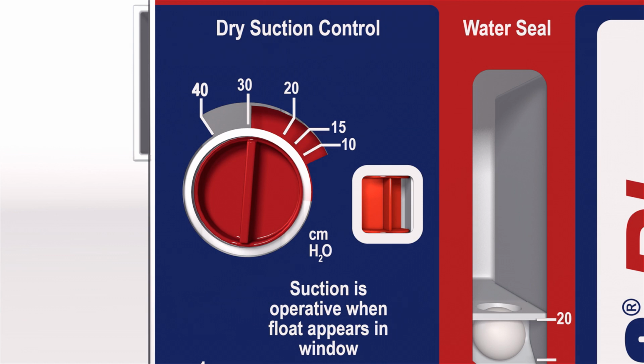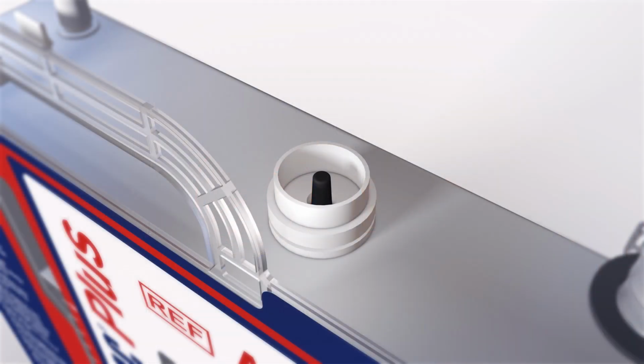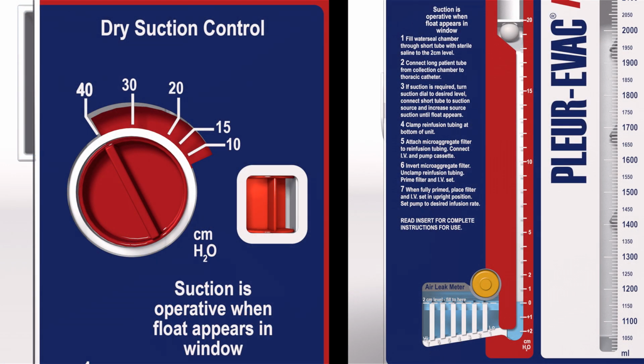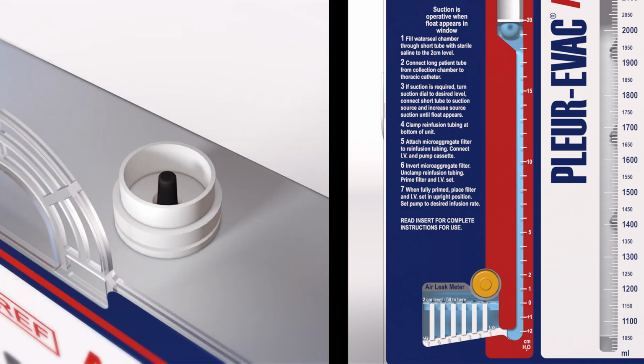Likewise, when changing prescribed suction level settings from a higher to lower level, patient negativity is likely to remain at the higher level. When these types of unintentional high negativity occur, the negativity can be reduced by depressing the manual filtered high negativity relief valve. For example, when turning the dial from a higher to a lower suction level setting, the water in the water seal will rise, indicating the patient's negative pressure remains at their originally imposed level, unless the patient has an air leak. To manually adjust the negativity to the new setting, depress the manual filtered high negativity relief valve.